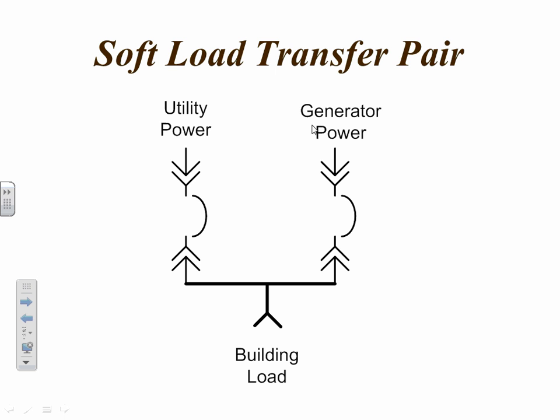Utility calls and says, run your generator set. So we start the generator set, and we have paralleling controls in this box that look at the utility. It adjusts through the governing system and the fuel to match the frequency, so we're in sync with the utility. And we have controls in there to automatically adjust the amplitude of the voltage so we can match the utility voltage. So we've matched the speed and the frequency. We're synchronized with the utility.